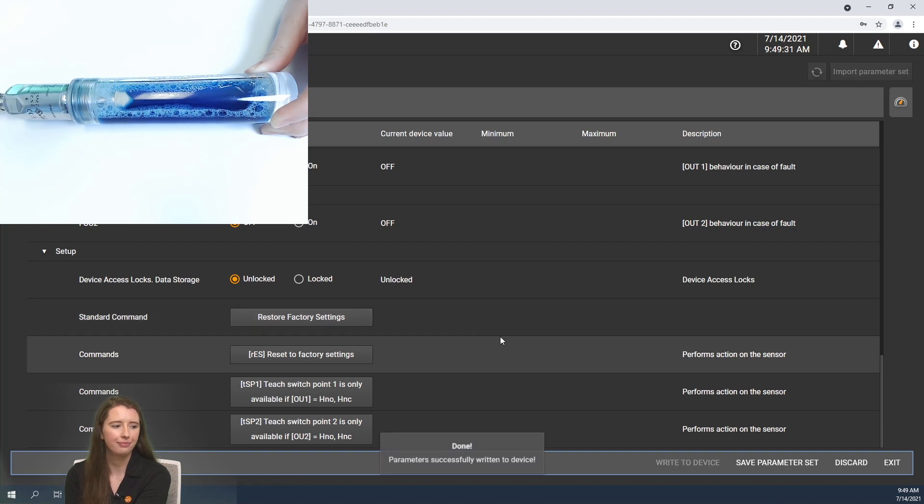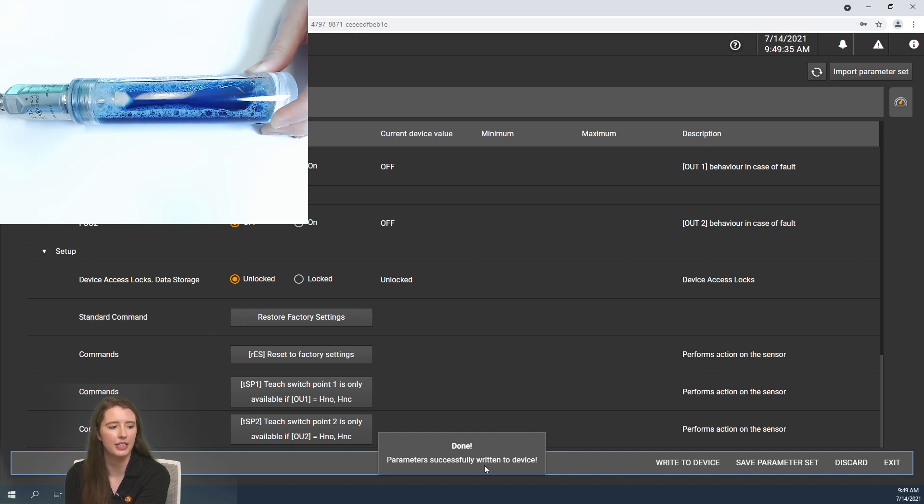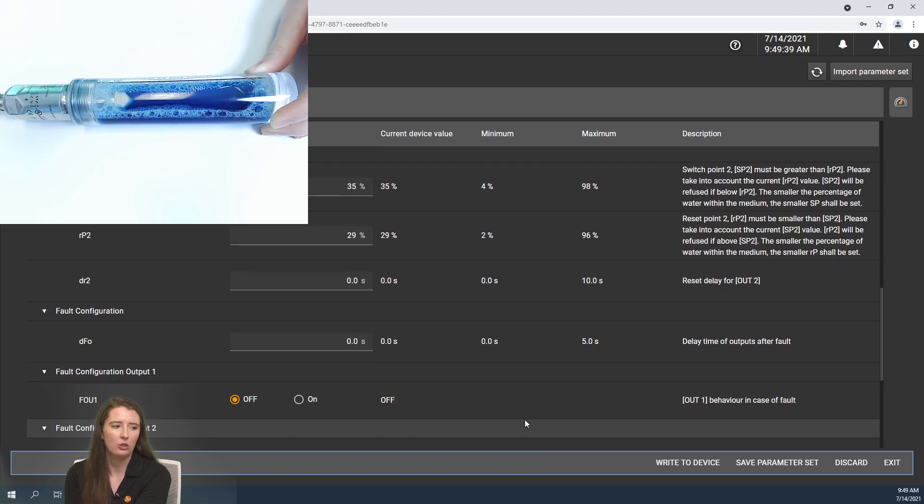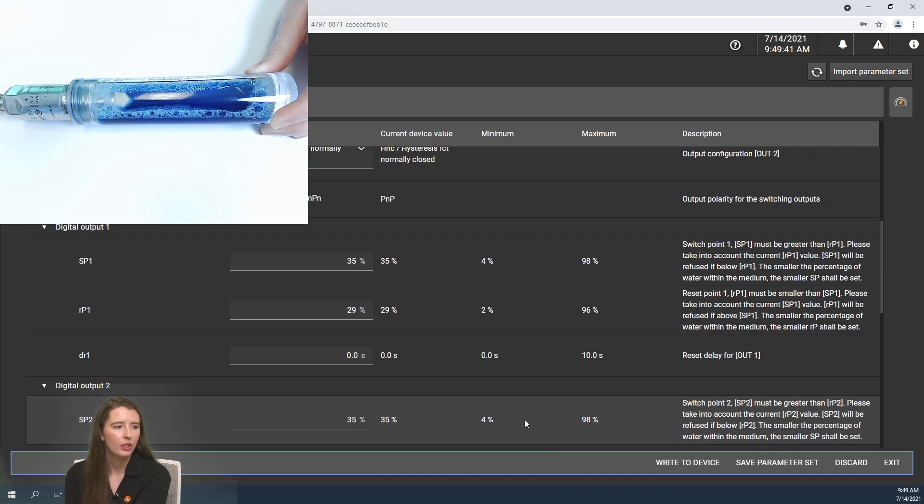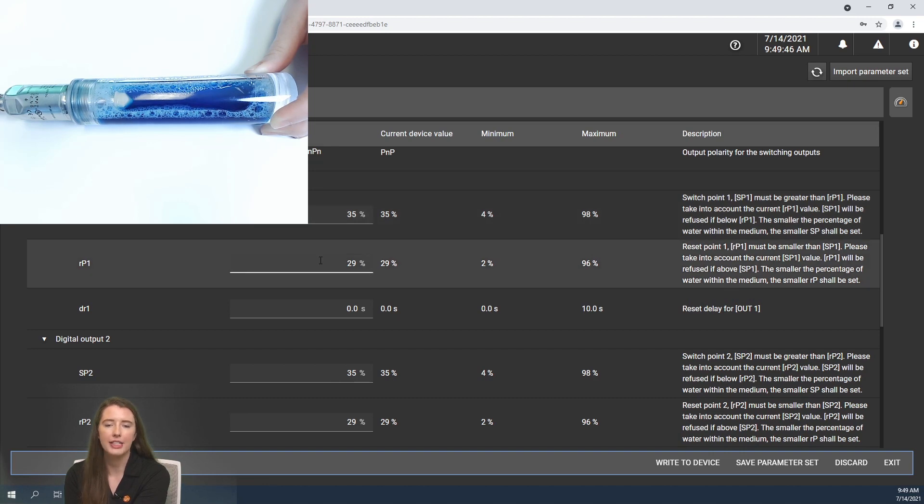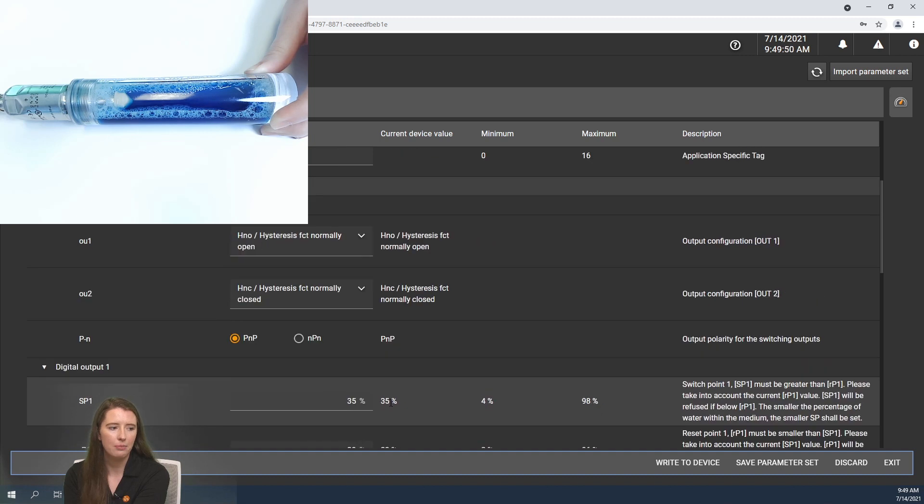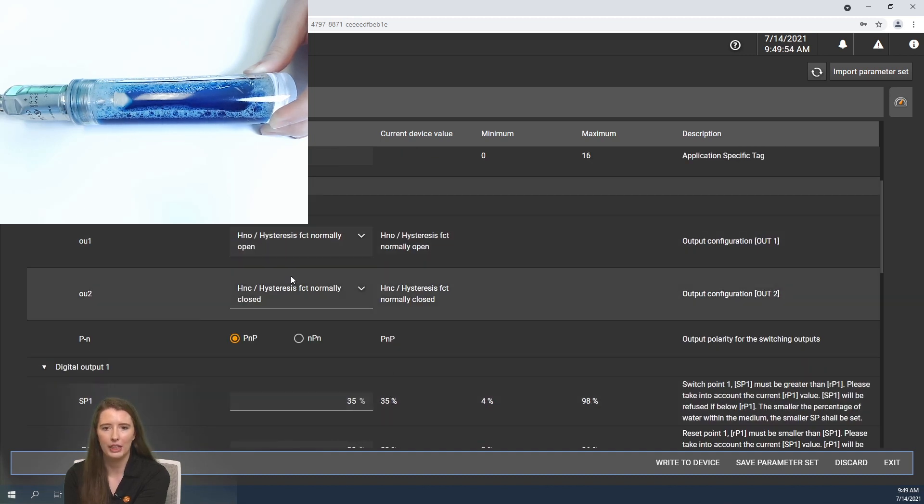So I'm going to press that now and you will see that when it has been successfully written to the sensor, a done window will pop up in the bottom. Now if I scroll back to the top you can see that digital output 1 the set point is set for 35% and the reset point is set for 29%. Output 2 also has the same settings but output 1 is normally open and output 2 is normally closed.